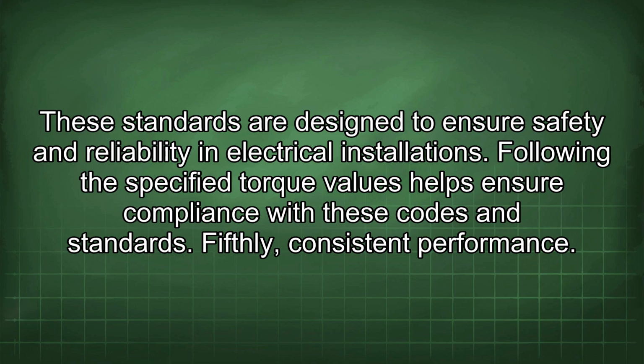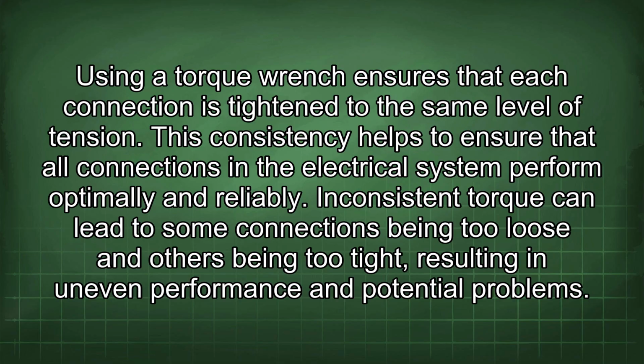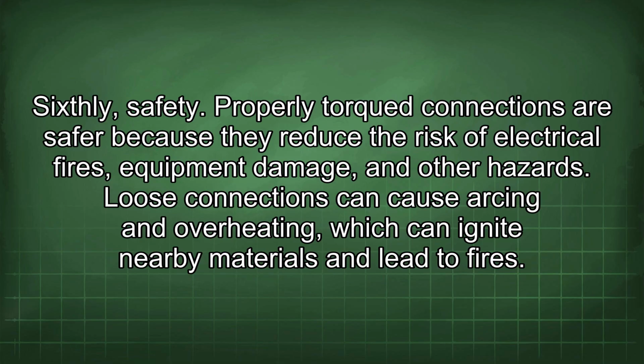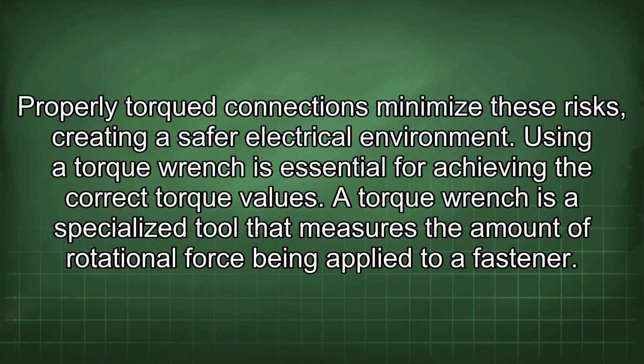Fifthly, consistent performance. Using a torque wrench ensures that each connection is tightened to the same level of tension. This consistency helps to ensure that all connections in the electrical system perform optimally and reliably. Inconsistent torque can lead to some connections being too loose and others being too tight, resulting in uneven performance and potential problems. Sixthly, safety. Properly torqued connections are safer because they reduce the risk of electrical fires, equipment damage, and other hazards. Loose connections can cause arcing and overheating, which can ignite nearby materials and lead to fires. Properly torqued connections minimize these risks, creating a safer electrical environment.